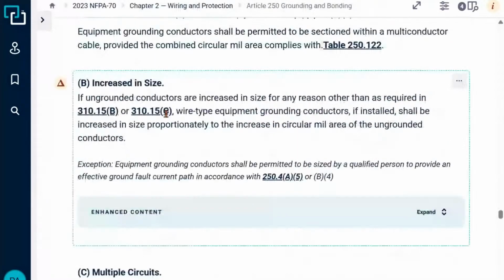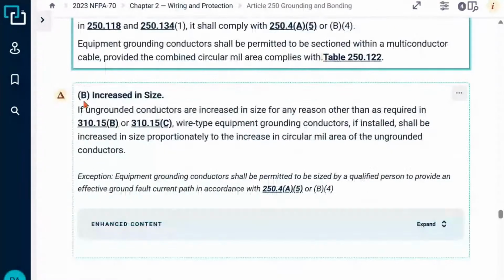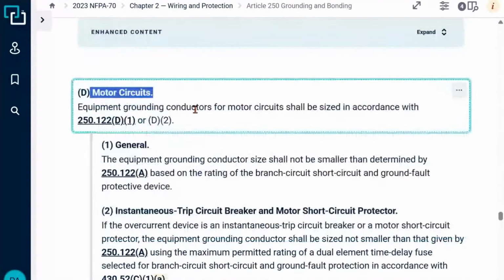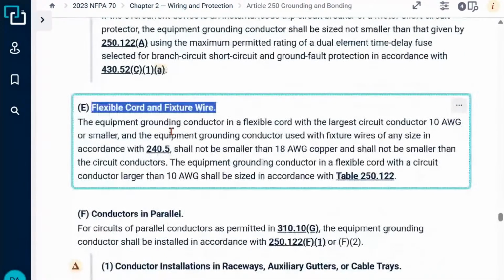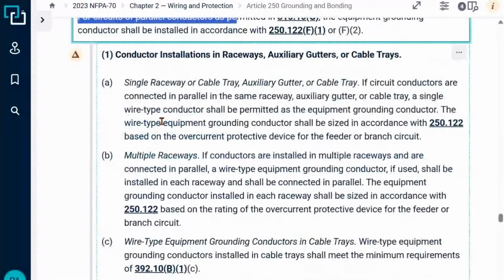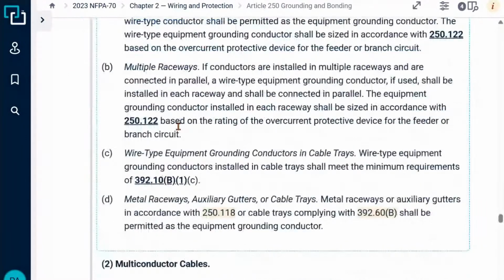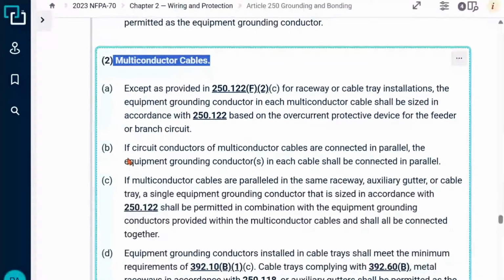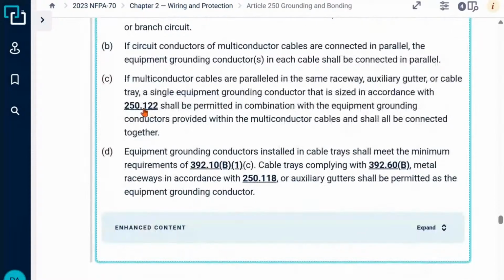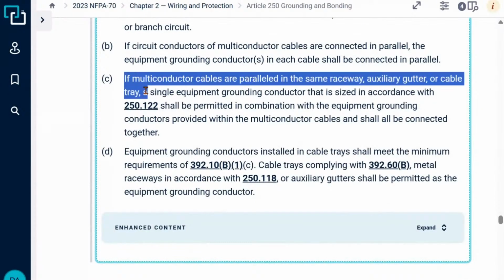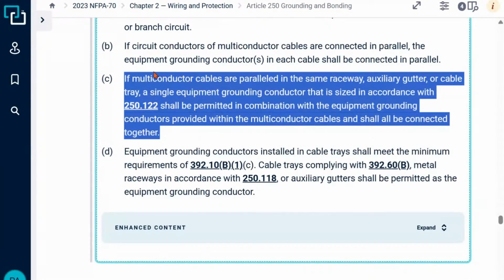And again, we've got all these different requirements down here, which at some point we'll go over. And there's your paralleling requirements, right? Remember I told you F, down here. Multi-conductor cables right here. That's if you're paralleling multi-conductor cables, like we just talked about, in a cable tray, for example, is one of the ways. And this is the one you have to pay more attention to. This one right here.